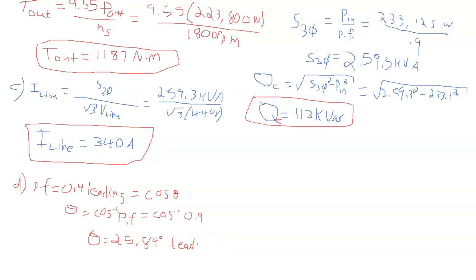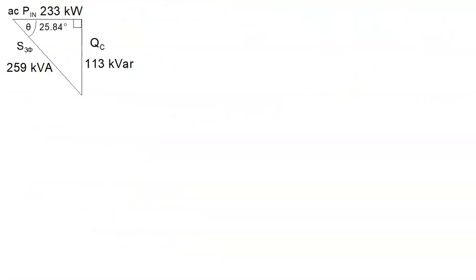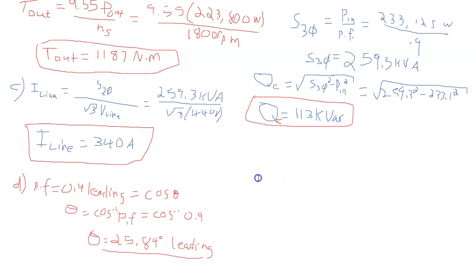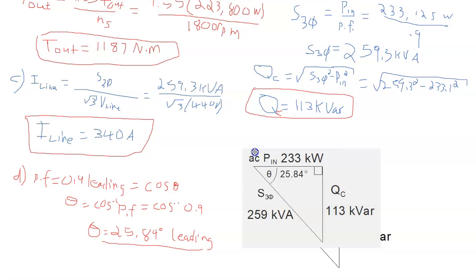So now we were asked to sketch the power triangle. Instead of me trying to draw it here inside of OneNote, I pulled in a pre-drawn one. And so I'll just go ahead now and copy that over. And so here is the power triangle. Now I put in AC power in as 233 kilowatts, my QC as 113 kVAR, my S3 phase as 259 kVA, and my theta as 25.84 degrees. And remember, the triangle points down because it's a capacitive triangle, or a leading triangle.